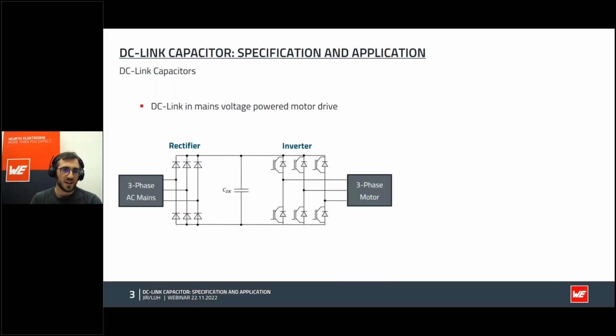DC-Link capacitors are traditionally called like this because they are placed between different power stages, and the DC interconnection requires some capacitance. So in English, this capacitor placement is also called a DC bus capacitor. This capacitance is required to stabilize the DC voltage, as well as providing some energy buffering for the power stage. Let's look at this example of an inverter powered by three-phase AC mains voltage. In the middle, between the rectifier and the inverter, you can see the DC bus, the DC-Link capacitor, and this is the placement of DC-Link.